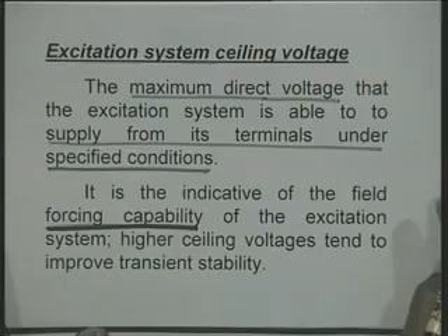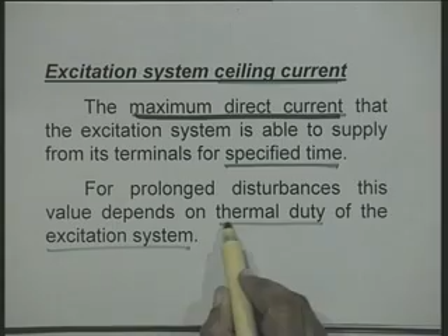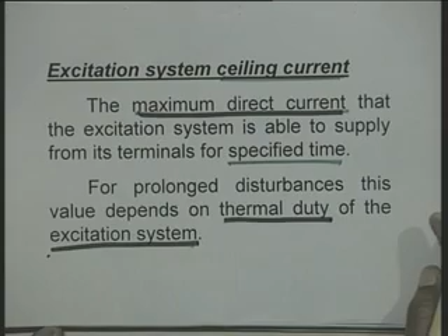The next term is the excitation system ceiling current. The maximum direct current that the excitation system is able to supply from its terminals for a specified time. Therefore, time is a constraint here. For a short time, it can supply current more than the rated value. For prolonged disturbances, this value depends on the thermal duty of the excitation system. In typical excitation systems, the ceiling current is of the order of 1.6 times the rated current.